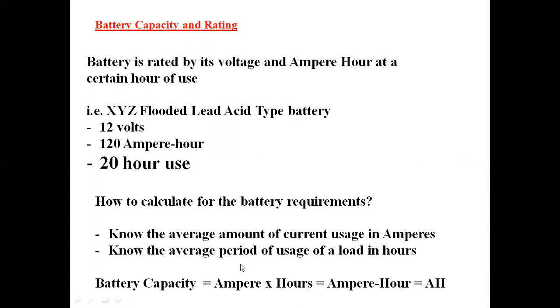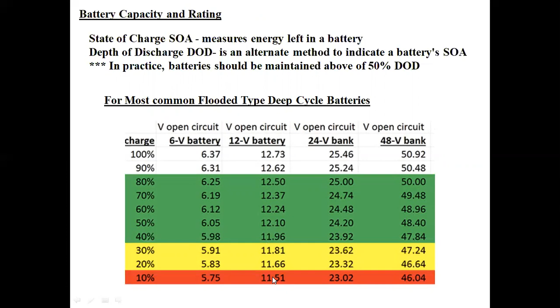So these are for the common flooded type deep cycle batteries. Yung open circuit volt niya andi dito. So for a 12-volt battery, yung floating charge niya kapag fully charged na siya is 12.73. Then the depth of discharge at 50% is 12.10 and yung almost drain ka na for 10% is 11.51.